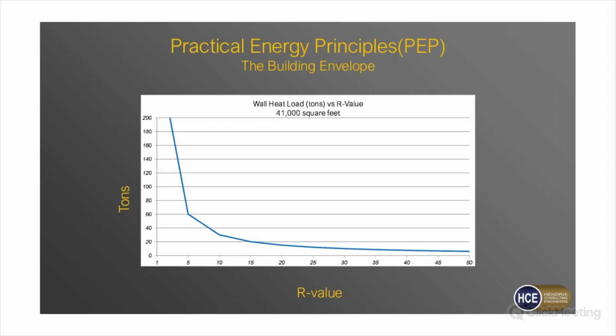When we're talking about heat load and R value, a lot of y'all may not look at this stuff every day. So I made this graph using the square footage of wall for a typical classroom wing, not the whole school. You'll see tons of air conditioning, or load, on the vertical axis and R value on the horizontal axis. As the R value gets smaller, the tonnage required to offset that heat load goes up.